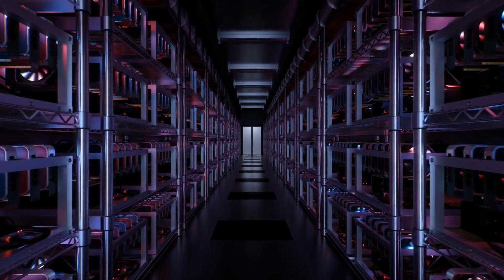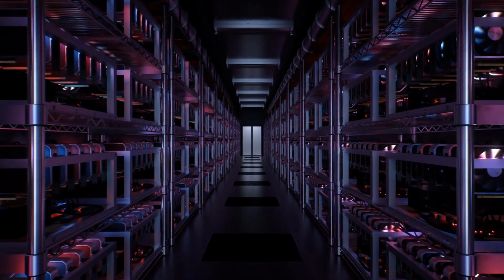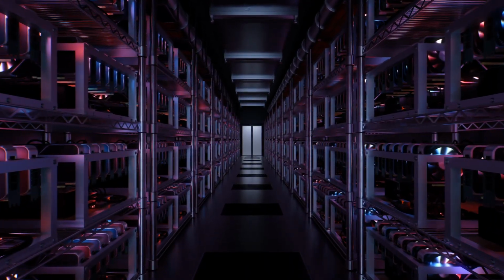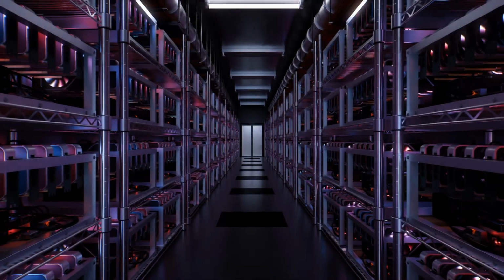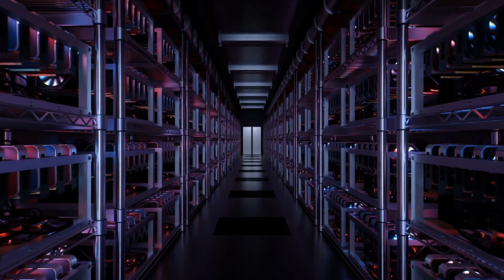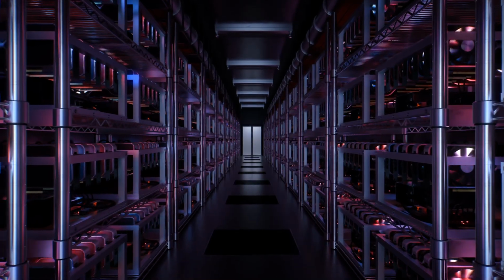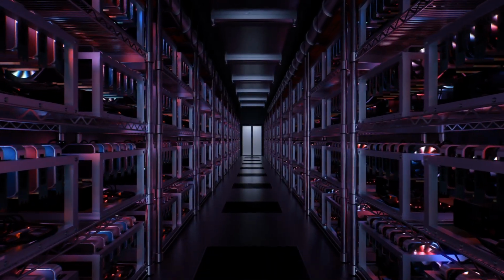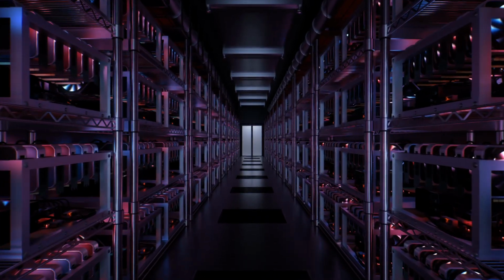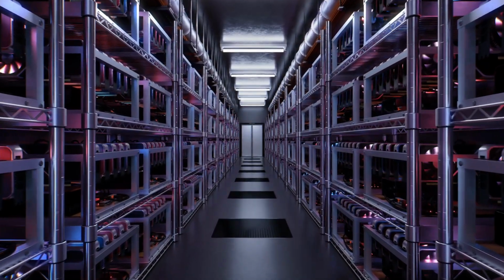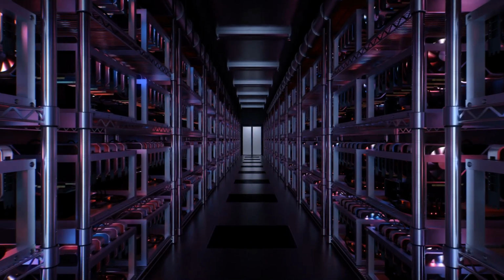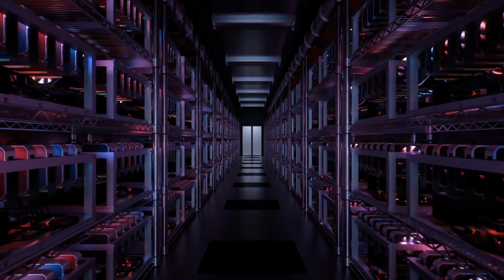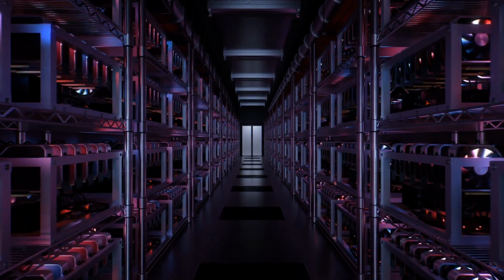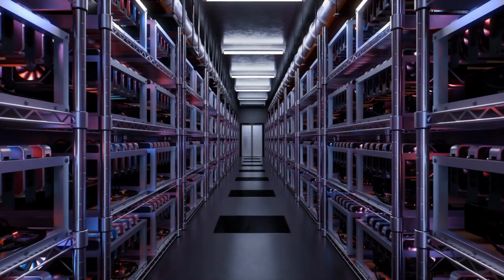For context, the tires on your car are probably inflated to about 35 psi. So the primary loop is pushing an immense volume of water, about 317 gallons a minute, at 4 times the pressure of a car tire. Inside a server room. Right. And the water itself is relatively rough. A 300 micrometer filter will catch rust flakes, sand, or large debris coming from the city pipes, but it allows microscopic elements to just pass right through. Right, it's not perfectly pure.